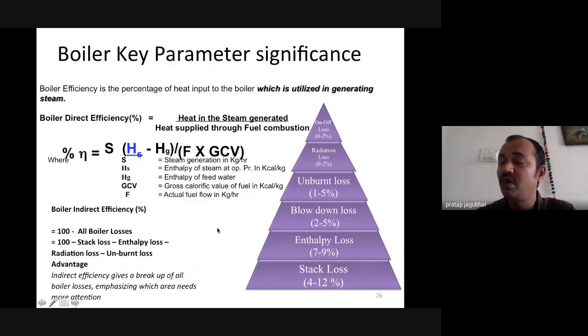Now, to go into more detail on the control and instrumentation part for the boiler, another question comes to mind: what are we going to do with this instrumentation and control? The better judgment is that we need to identify the economy of the boiler, and that economy is nothing but the boiler efficiency. The boiler efficiency can be called the direct efficiency. The direct efficiency is simply the percentage of the heat input in the form of fuel which is utilized to generate the heat output in the form of steam.